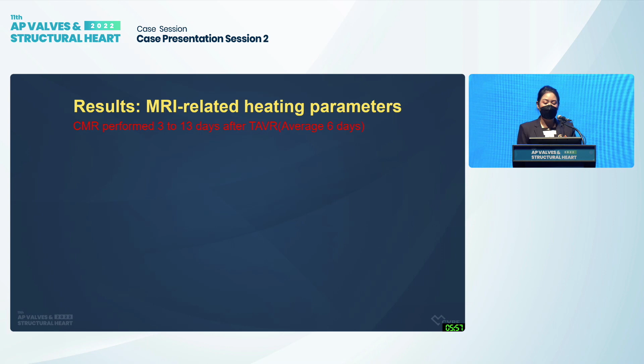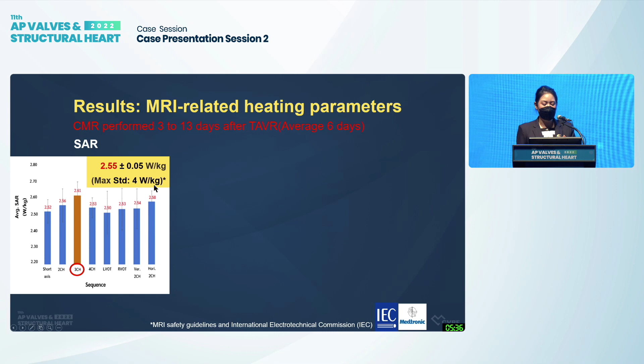The first value is SAR. The 3-chamber view has the highest value, but the average is 2.55. The IEC and Medtronic MRI safety guideline accept a maximum of 4 watts per kilo. Our study is just 2.55. The second one is B1+RMS. The 3-chamber view is also the highest value, but the average is 2.01 microtesla. The accepted maximum is 2.8 microtesla. The last one is SED.